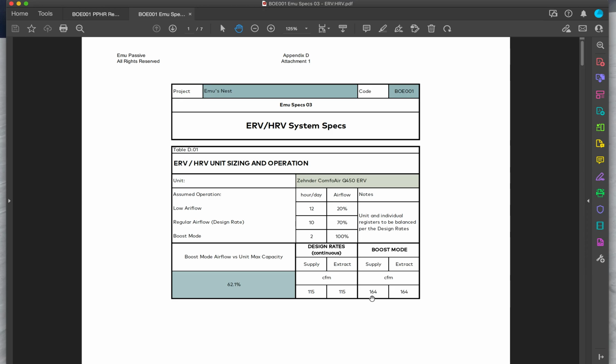Same for the boost mode. Say I take a shower, I want the whole building to run more, so I can boost it up from 115 to 164. That is just my design rate. But again, the total supply equals the total extraction. So if you have an HVAC contractor that recommends extracting more than you supply, or vice versa, please be aware you want the two to be balanced and the same. So these are the ventilation rates that at commissioning you will want to double check and commission to.